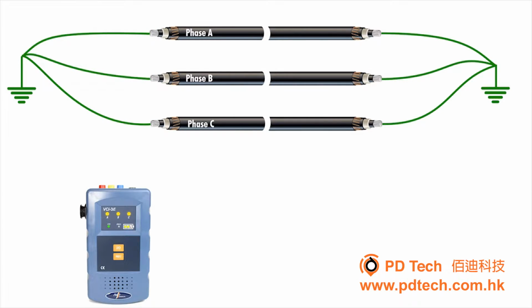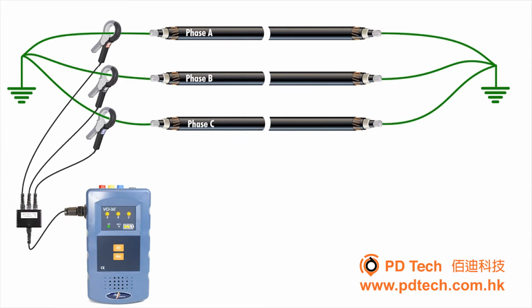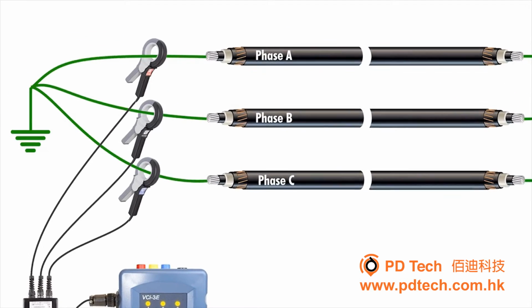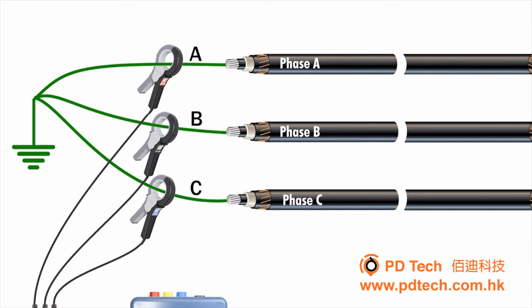For more convenient testing setup, use the magnetic injection clamp-ons. Simply connect the clamps lead to the transmitter and install the magnetic clamps around the conductors A, B, and C. Again, it's important to match the clamp phase ID A, B, and C with the correct cable phase tagging. Clamps should all be facing the same direction, such as the further end of the cable.